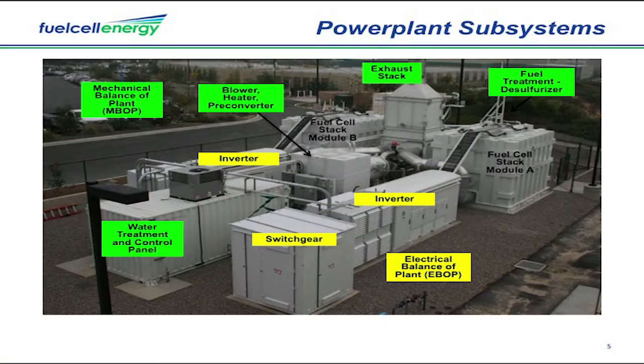This is a bit of a view of what a typical 2.8 megawatt fuel cell power plant looks like. It has those 2 fuel cell stack modules, each netting 1.4, so 2.8 megawatts total. The mechanical equipment, which we call the MBOP, mechanical balance of plant, is just heat exchangers, air supply blowers, startup heater, that kind of thing. The electrical equipment, the EBOP, electrical balance of plant, is DC to AC power conversion, because direct current is what comes out of a fuel cell. It's like a big battery, with switchgear and so forth for interface with the grid. So that's a complete system that takes pipeline quality natural gas or biogas and converts it to electricity.